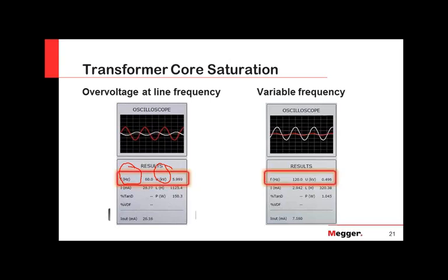Six kV. And you can see the sinusoidal is still there. There's no deformation, there's no deviation. We're already on 8 kV, and you can see already that there's a little deviation on the peak of the wave.